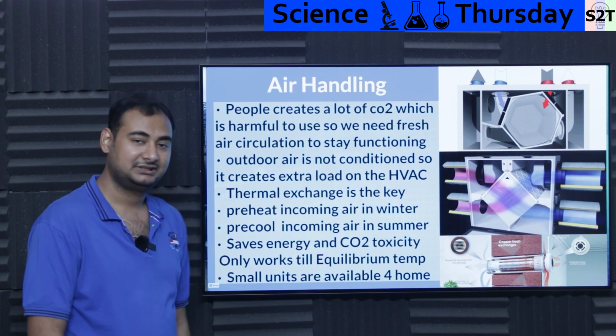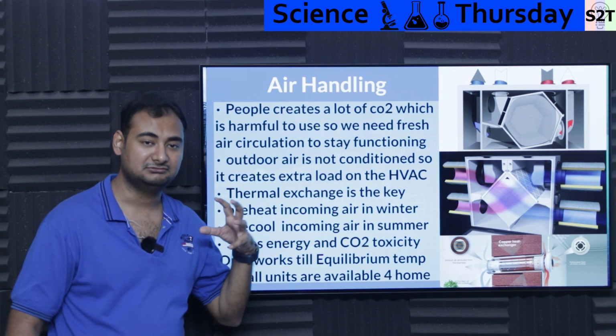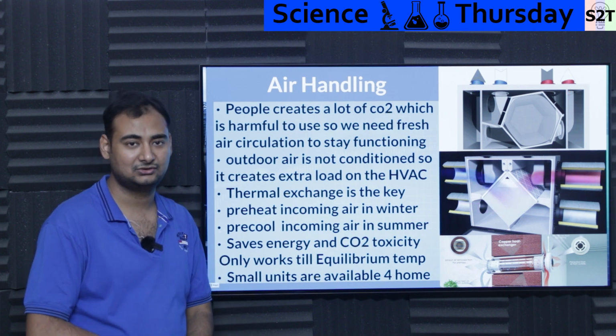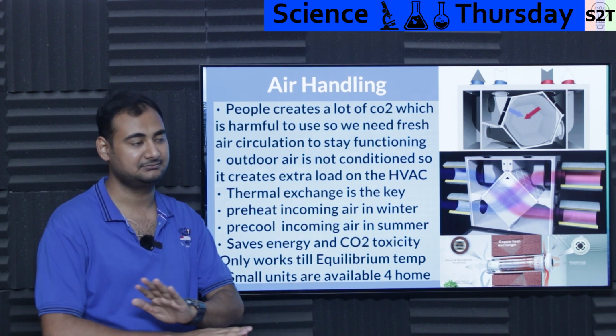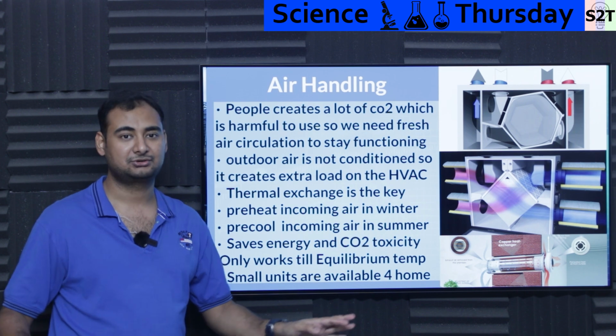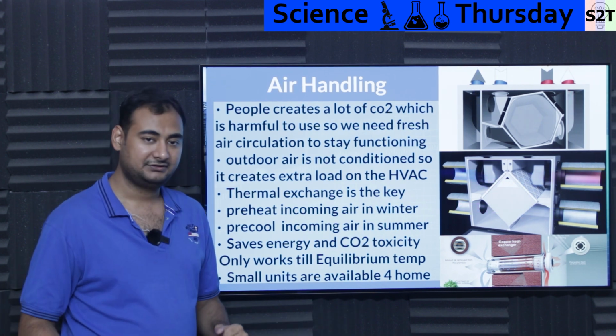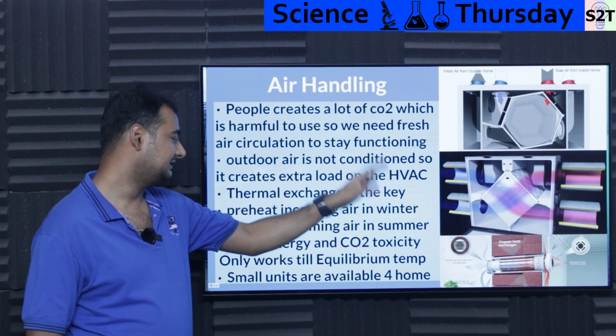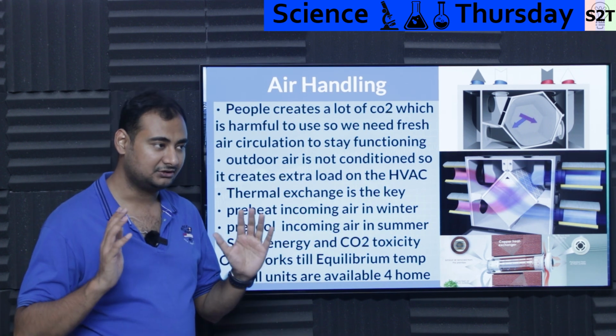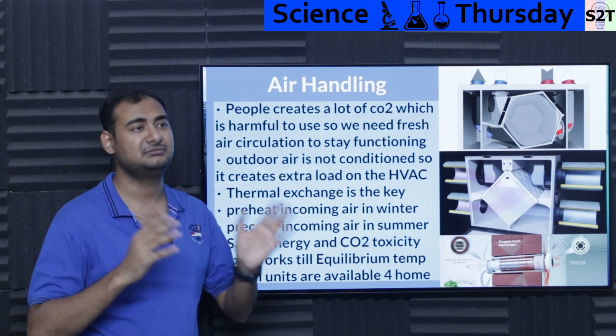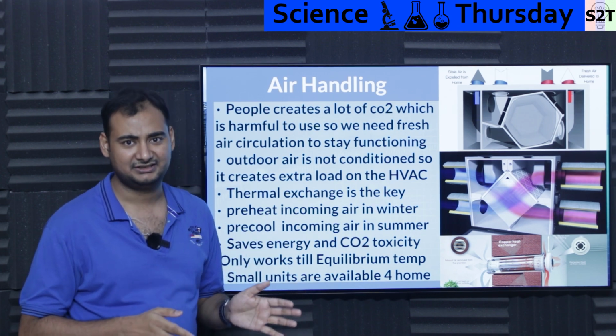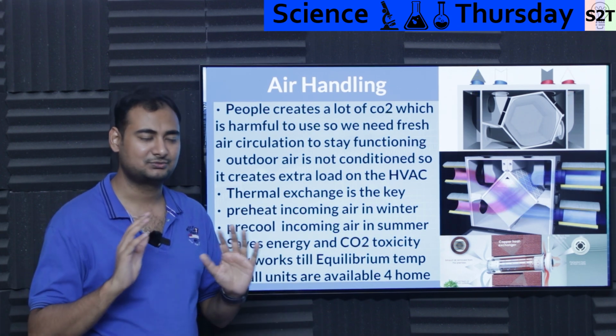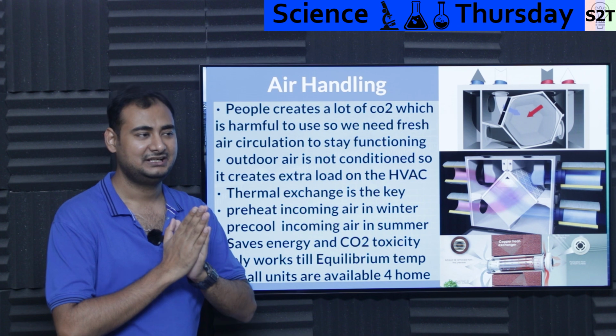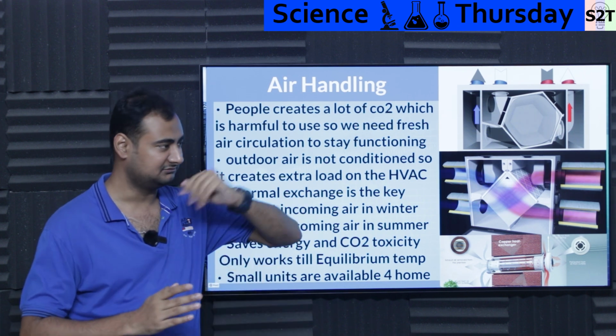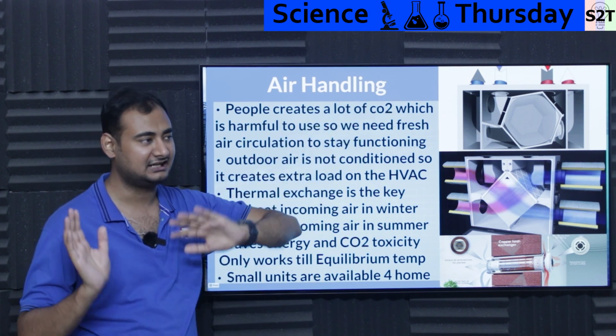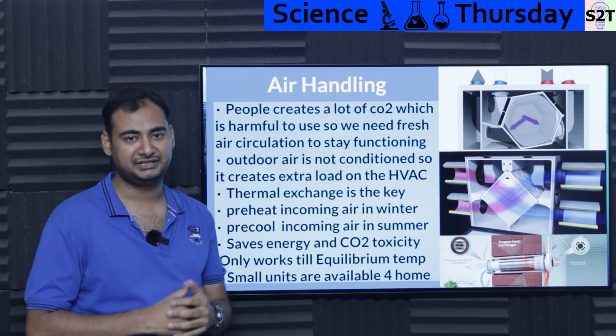So how do you take care of it? It creates a ginormous amount of thermal load on the air conditioning unit, and the air conditioner is like, I'm out, I'm flat out. So what we do is heat exchange. Heat exchange is the key, thermal exchange basically, where you are not mixing air. It can be done, some designs do mix it, but generally it's not preferred. Most of the time, the idea is do not mix airs if you can avoid it. Just let the bad air out, let the high CO2 air go, and bring in fresh air.